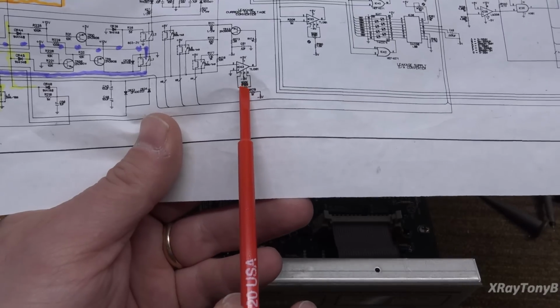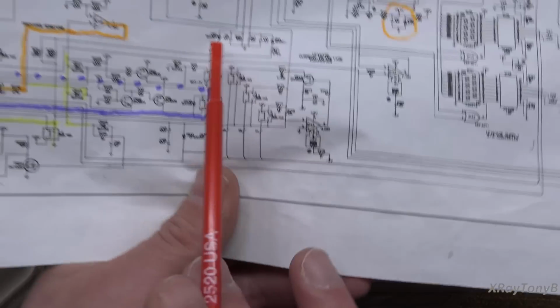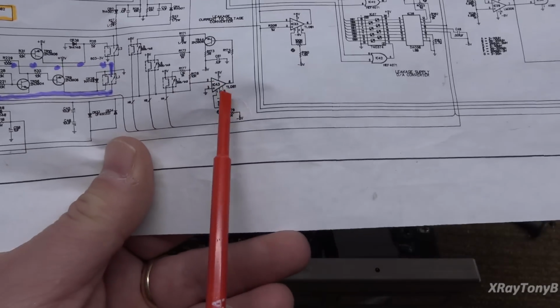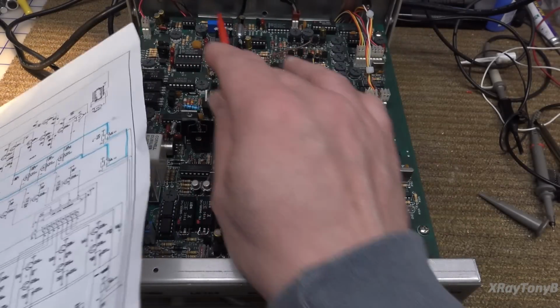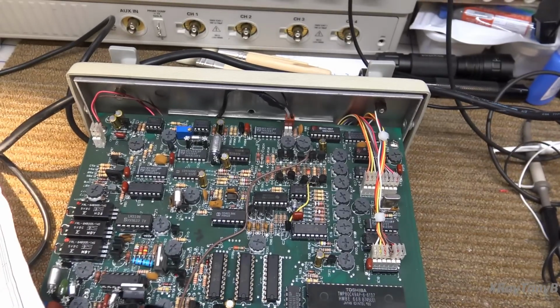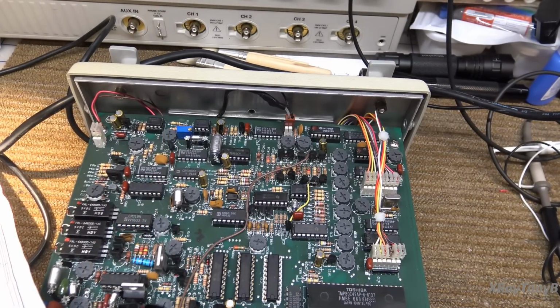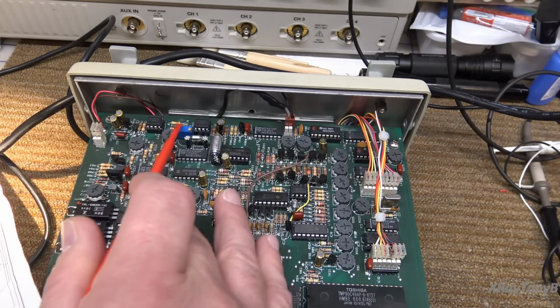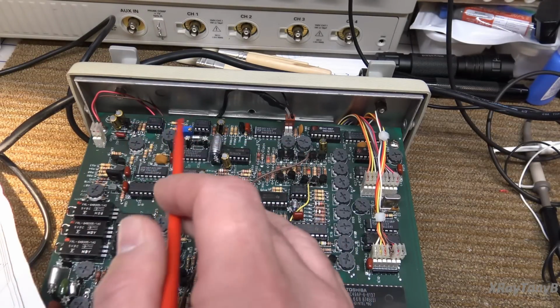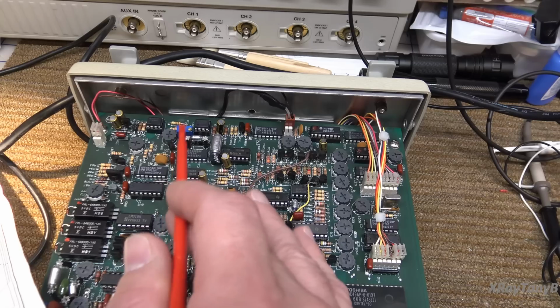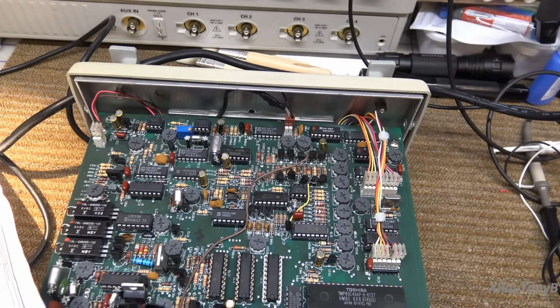In addition, there are some null points that you set in the calibration; we'll talk about that in another video. You have to set these to a null point. This one here on IC44 and IC43, the one which is this pot right here, is very, very sensitive. And if the pot is the least bit noisy, it makes it really hard, and this has to do with the dielectric absorption and the leakage calibration, or the ESR and the leakage calibration. So to make this easier to adjust, I removed the old 100K pot from here and installed this 10-turn 100K pot. It made it a lot easier to calibrate.